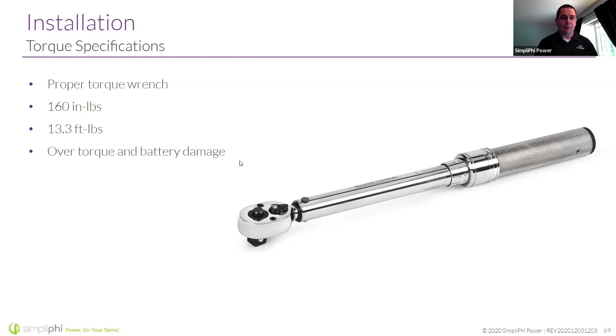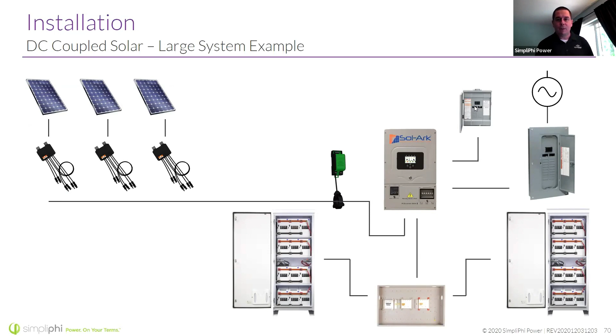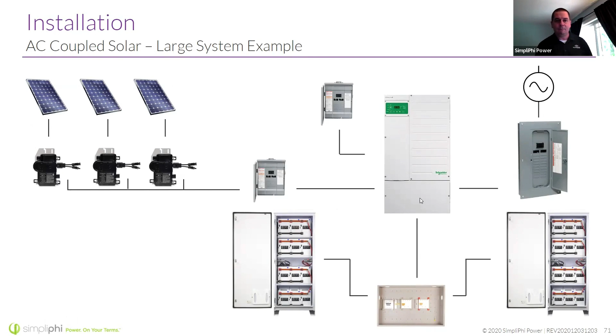A couple of system examples here. This is a DC coupled system with a solar array and rapid shutdown on the roof. We've got a couple of Boss cabinets wiring into one of those combiners from the previous slide. This is grid tied with a backed up load center. You can do the same thing with AC coupling, provided your inverter charger can handle it - got micro-inverters on the roof here.